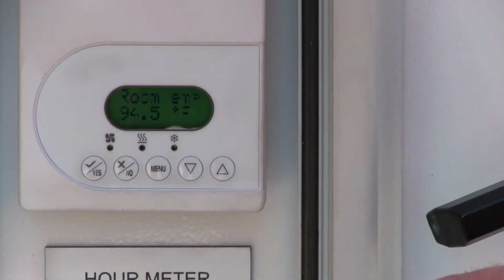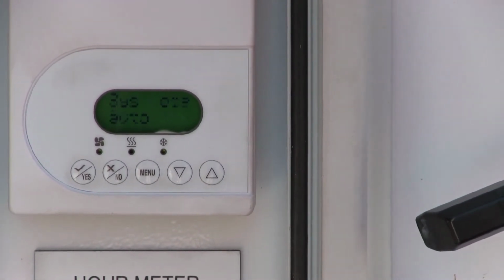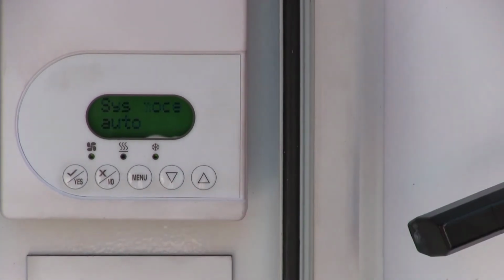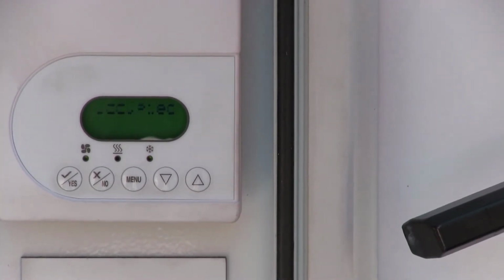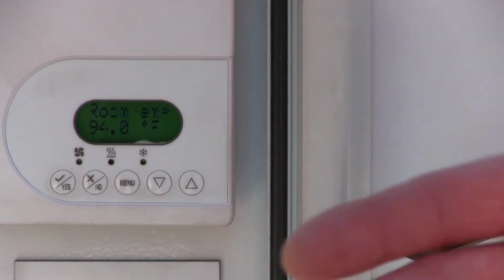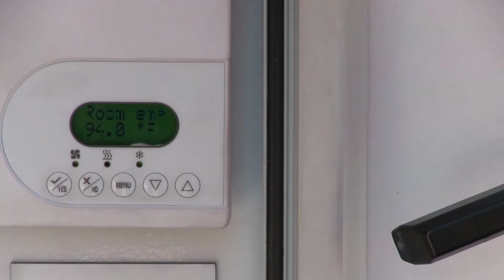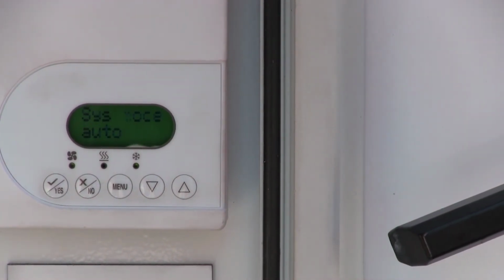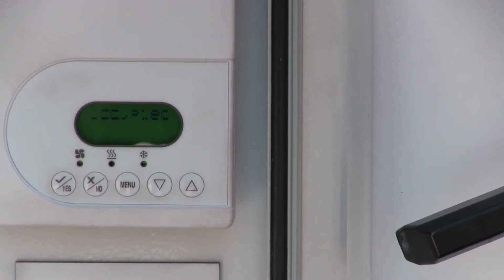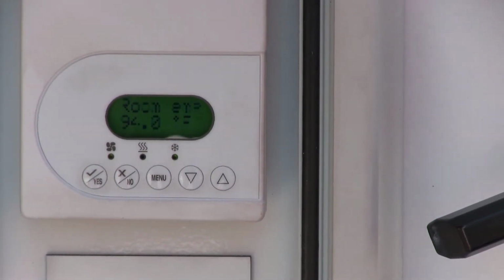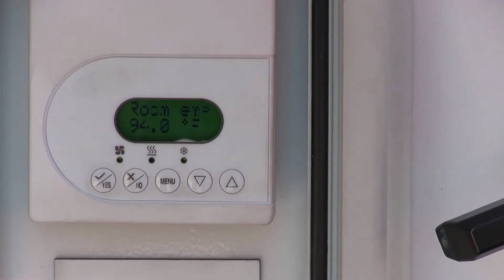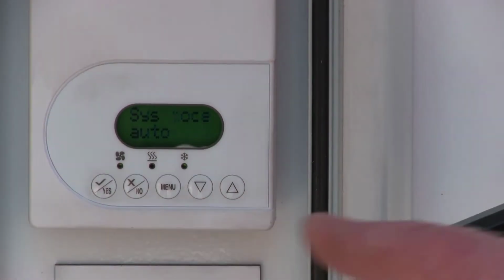So the system is going to cycle based on the inlet air temperature. That's where the sensor is for the thermostat, where our duct connection is. It's going to cycle between heat and cool as necessary. The machine's actually already running. It's in cooling, producing cold air down our ductwork there. And as the system temperature changes on the inlet, it'll automatically cycle between heat and cool.